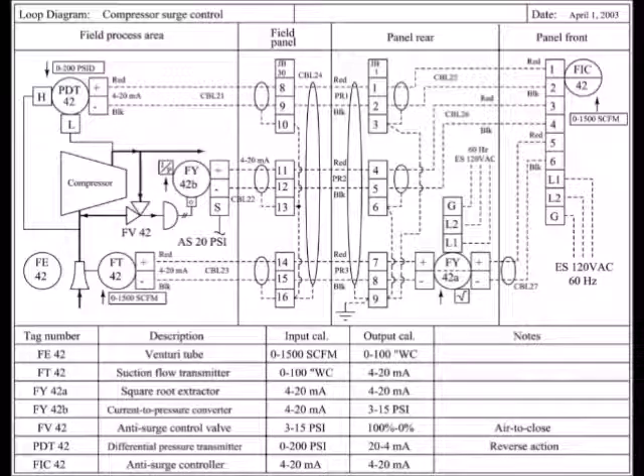In the second column, you can see the field panel, sometimes also known as remote I/O. The numbers represent the points on the terminal block and the field panel serves as an intermediate point for disconnecting and isolating cables, signal continuity checks and troubleshooting.